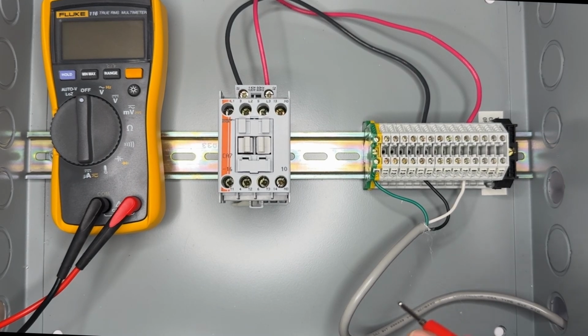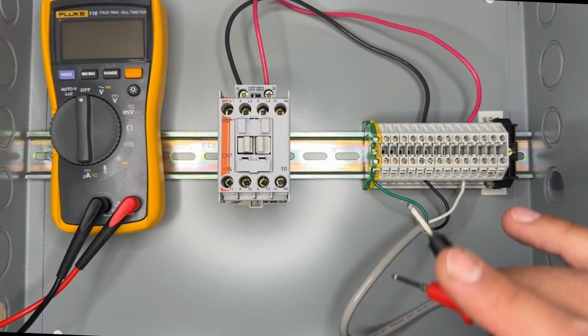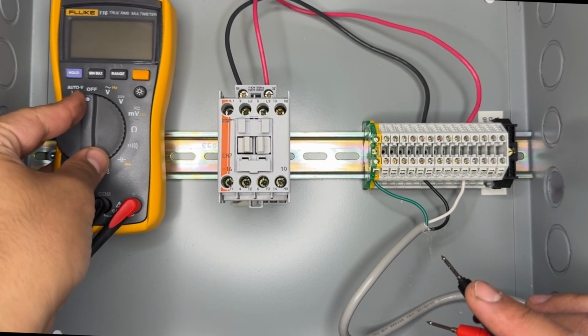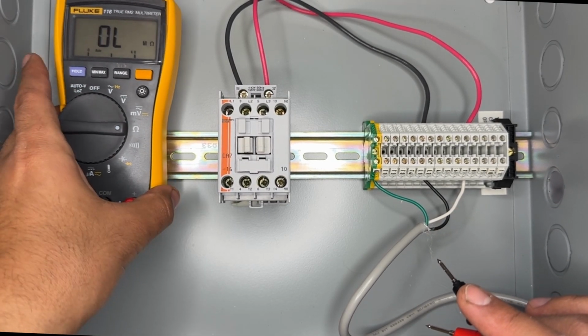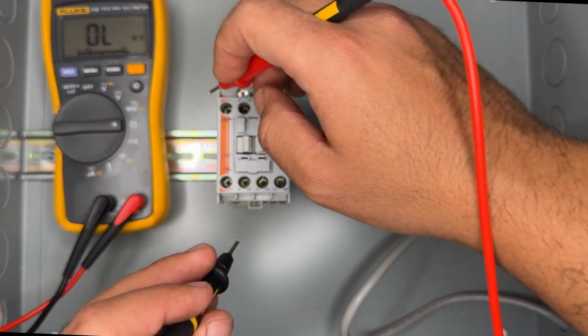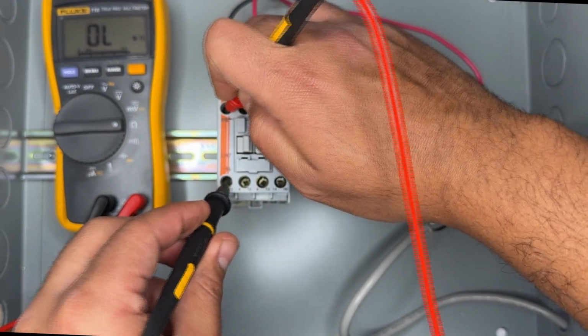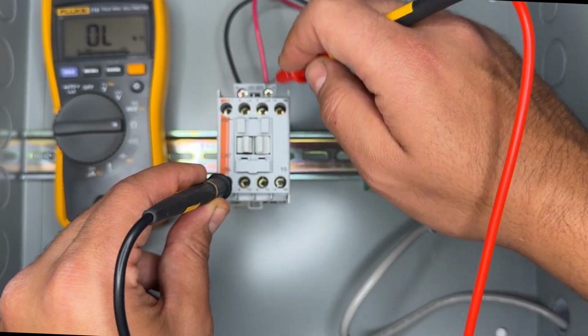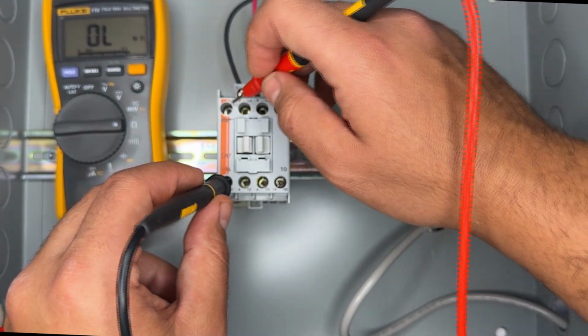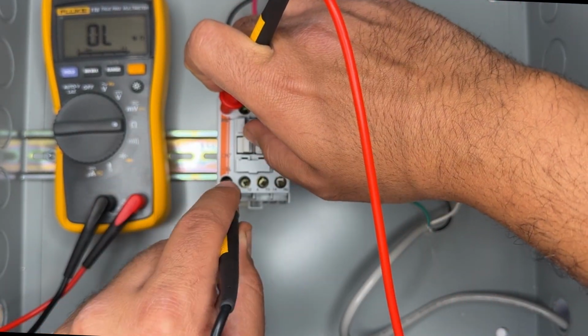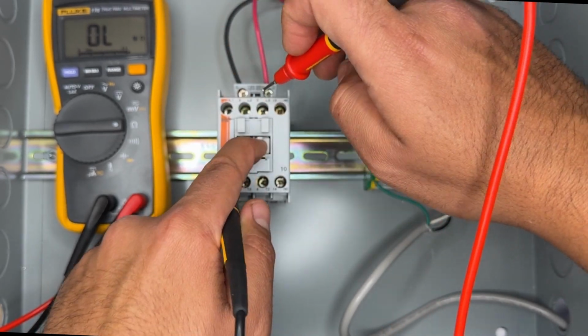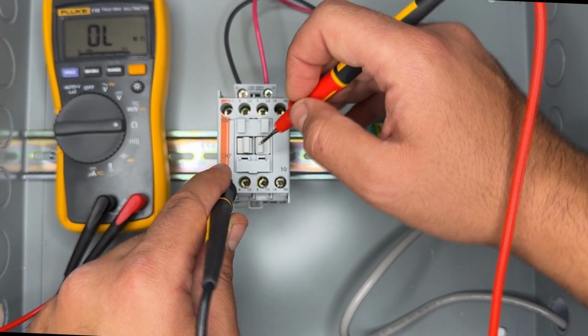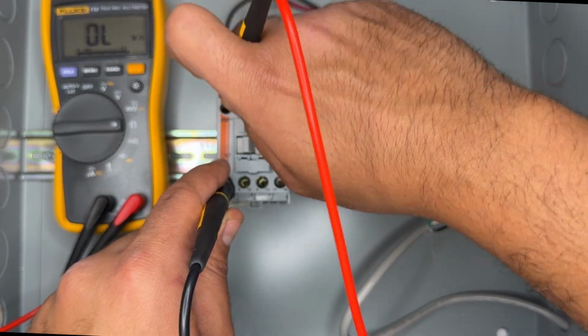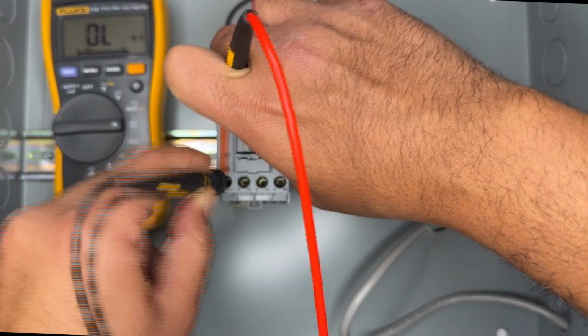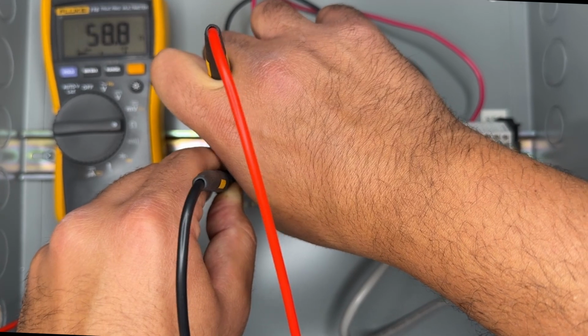Okay, so for the next test, we're going to be testing our contact resistance. So again, you want to make sure there's no power on your panel, and we're going to move our multimeter to ohms. And what we're going to do is check the resistance across each of these contacts, so from the line side to the load side. So one probe on each side, and you can manually push this plunger in. You may not be able to do that on a safety contactor, but you could do that on most contactors. So let's go ahead and see what that gives us.